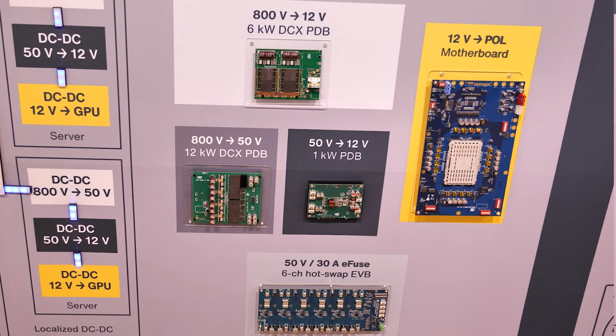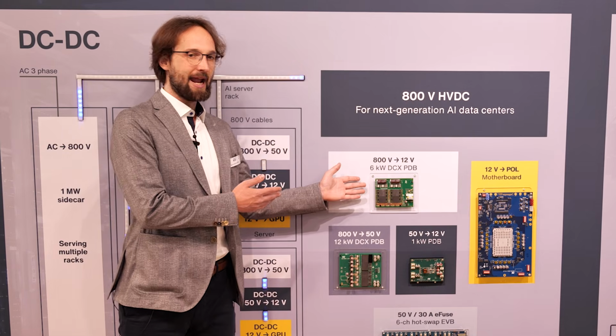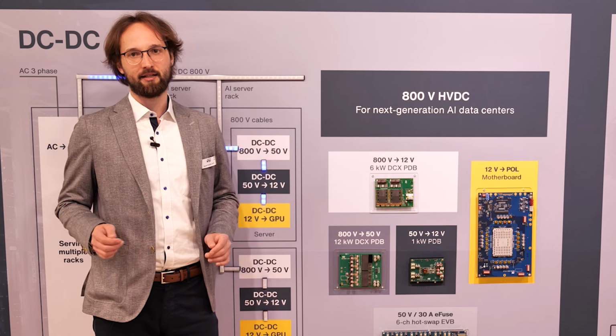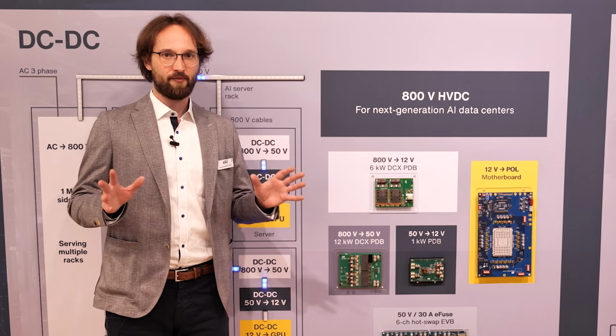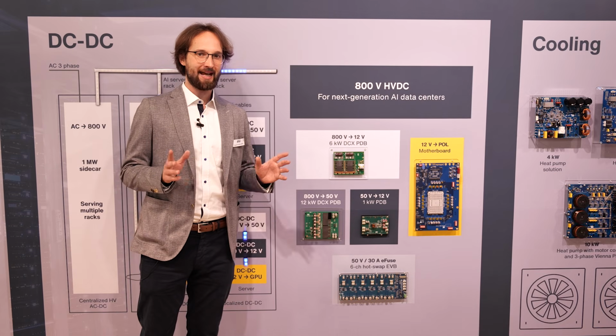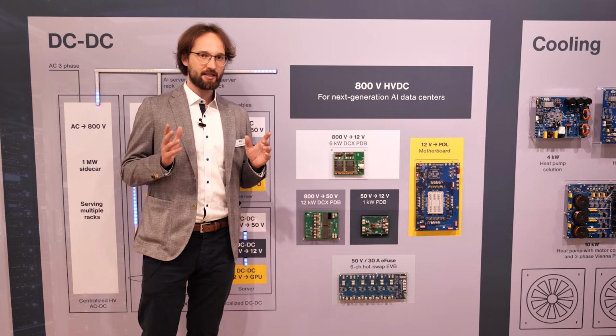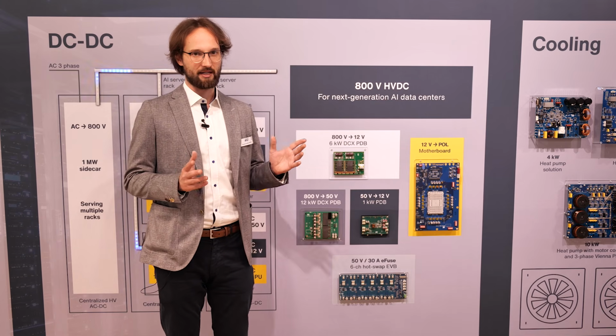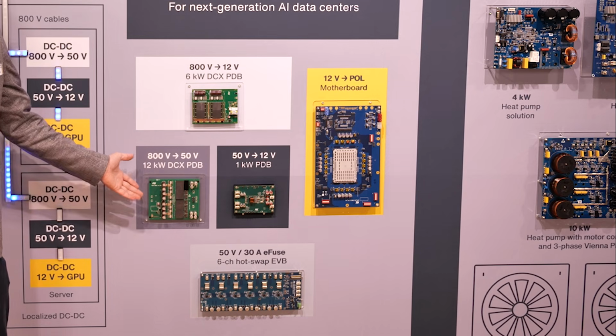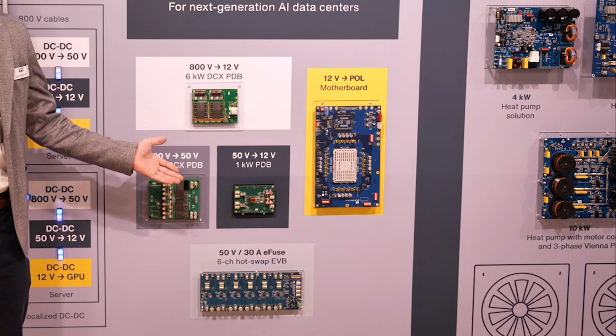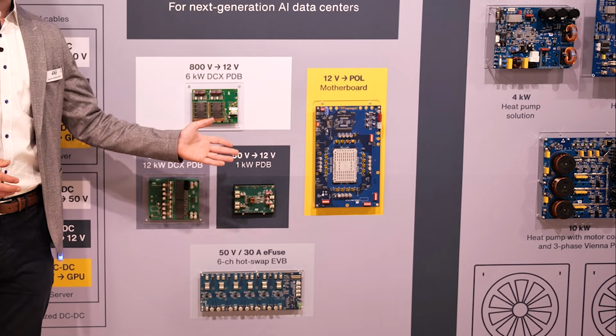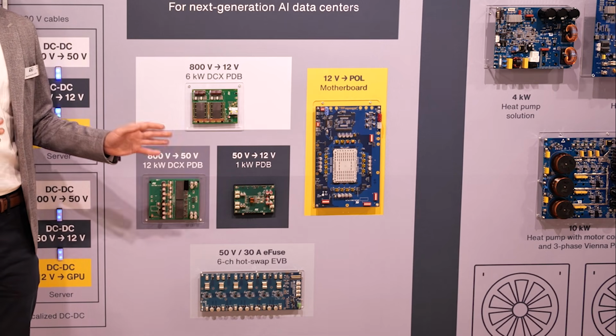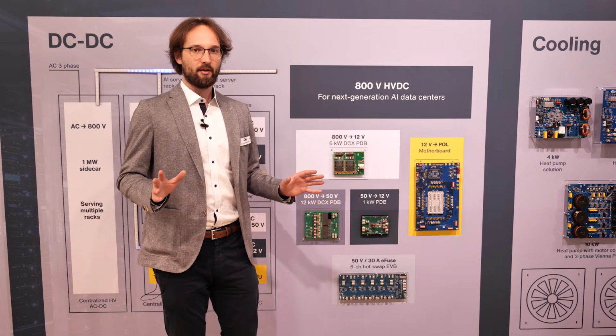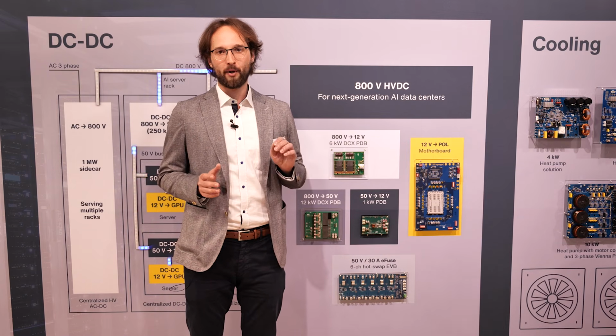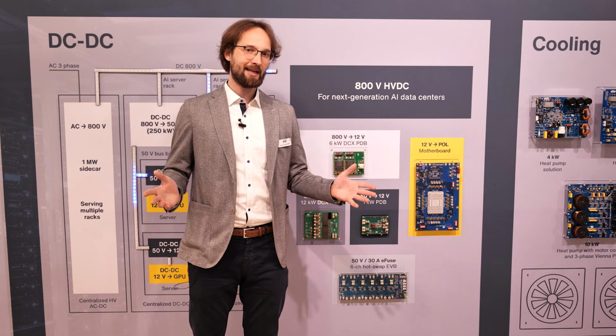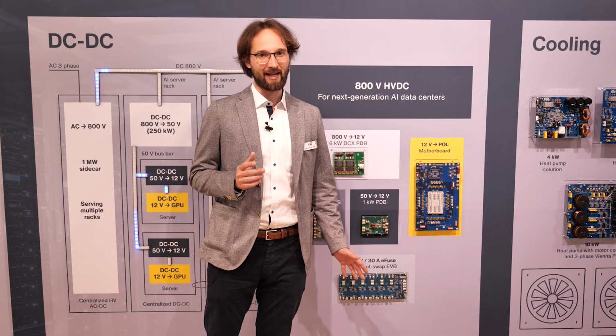These are the specific products for this architecture. The 800 volt down to 12 volt 6 kilowatt DCX power delivery board skips the 50 volt completely and offers direct conversion from the HVDC, representing the most advanced trend of this architecture. The 800 volt to 50 volt DCX 12 kilowatt and 50 volt to 12 volt 1 kilowatt represent a solution with a standard 50 volt rail. As these are made for extreme power density, up to 2.6 kilowatt per cubic inch, it is mainly gallium nitride handling the switching frequency of 1 megahertz.